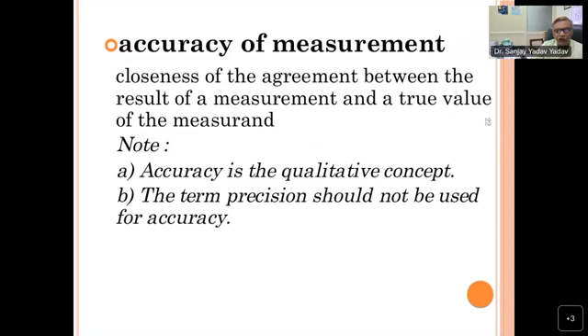Accuracy is the closeness of agreement between the result of measurement and the true value. Understand the implications of accuracy of measurement. Accuracy is purely a qualitative concept. The term precision should not be used in place of accuracy. Precision is basically the characterization of the standard deviation. So accuracy is the characteristic of the instrument, but uncertainty is the characteristic of the measurement. Please understand that logic.